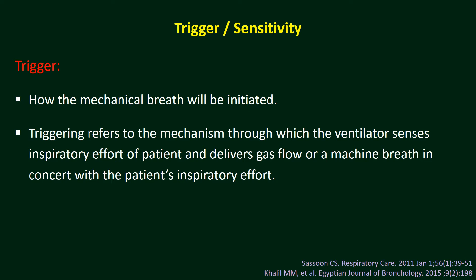If the patient does not take any breath, then the ventilator will deliver after a certain period of time as per the setting of the ventilator, or inspiratory time. So there are two types of trigger, a major classification: time trigger and patient trigger. Time trigger means the ventilator will initiate a breath according to the set frequency, independent of the patient's spontaneous breath.